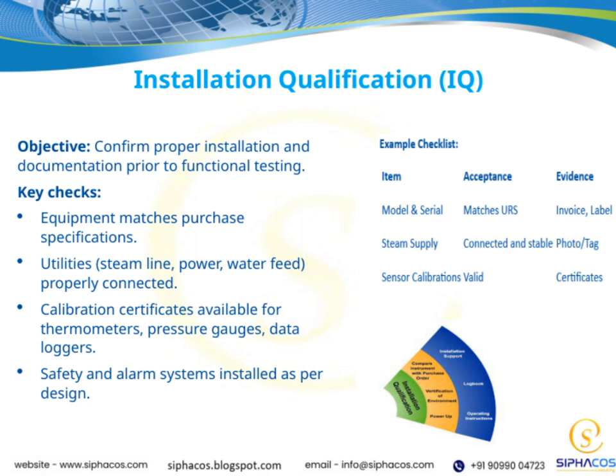Next, we need to confirm that utilities like steam lines, power supplies, and water feeds are properly connected. Proper connections are vital because they impact the equipment's performance and safety. If these aren't set up correctly, it could lead to issues down the line. We also check for calibration certificates for critical instruments like thermometers, pressure gauges, and data loggers. Having valid calibration certificates ensures that measurements are accurate and reliable, which is essential for maintaining quality and compliance.